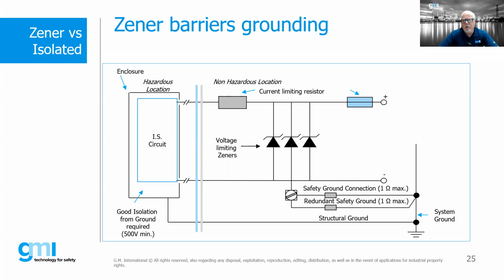The reason you will typically find in many cases a redundant safety ground is that there is a requirement to periodically check the resistance on our safety ground. So what we would do is have 2 connection points. We would remove one, make a connection point, test that ground, reconnect it, and then test the other one to make sure that we are truly achieving 1 ohm resistance or less.